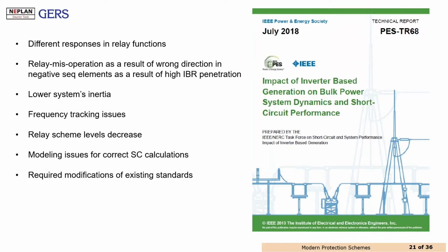You can see that in this kind of systems, the short circuit level decreased in comparison with the short circuit levels with synchronous machines. And the standards for the short circuit calculations, for sure, as I presented before, were based mainly on synchronous and turbo machine generation.